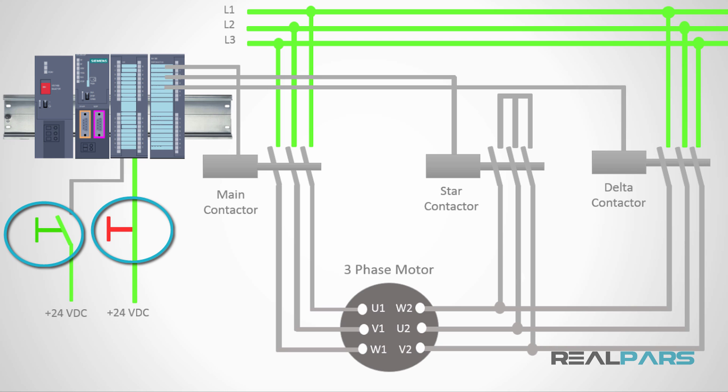Now, assuming the start switch is connected to the first input of the digital input module, the address that I can use for this switch in the program is I0.0 and assuming the stop switch is connected to the next input of the same module, its address would be I0.1.